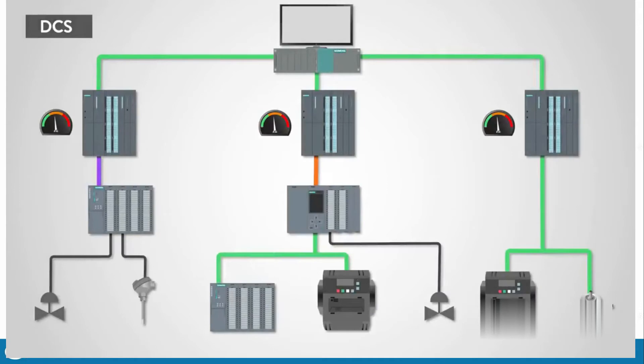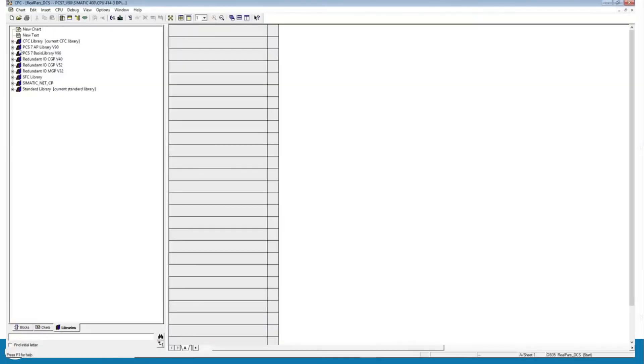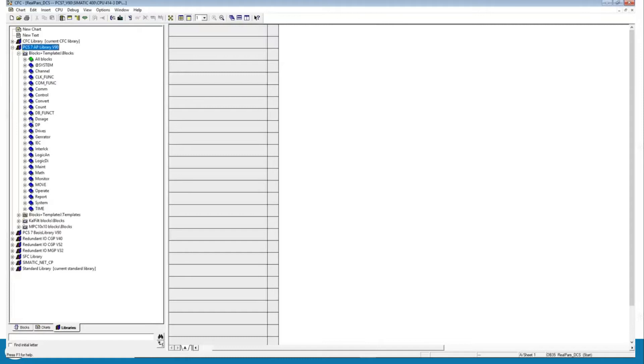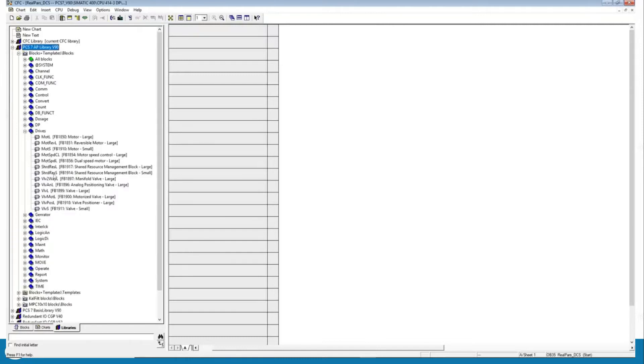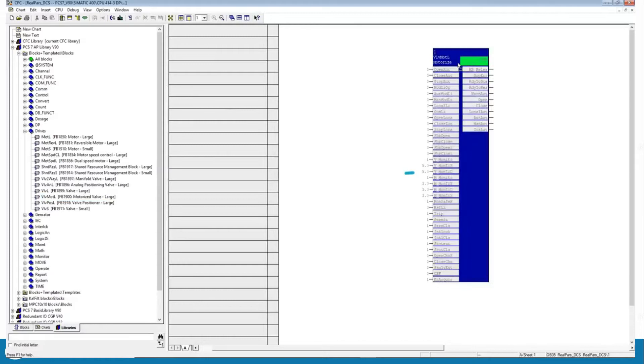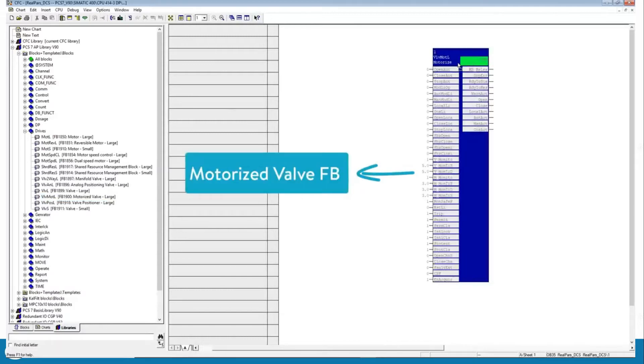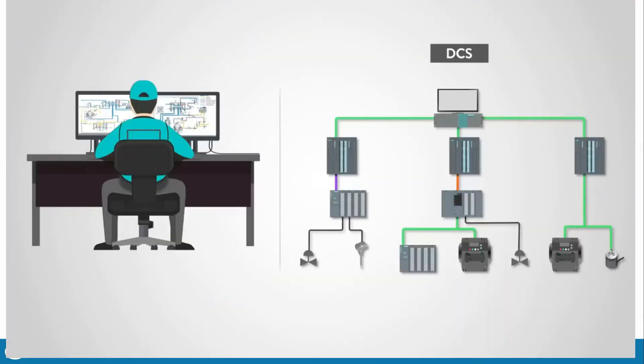A DCS is used for continuous complex controls. They have an integrated control center, much like a SCADA, which is the core of the system versus the processors in a PLC system. The DCS has a number of predefined functions that come ready to customize and deploy for various applications. Processing times are somewhat slower, and operators interact with the control system via an integrated graphical display.